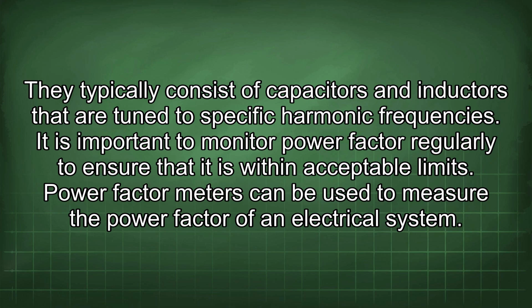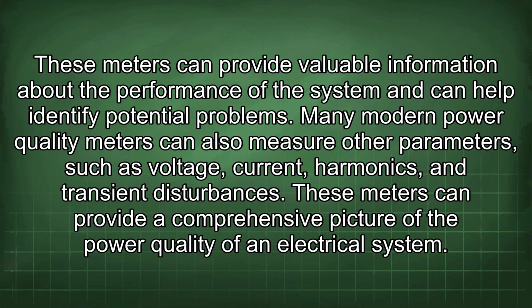It is important to monitor power factor regularly to ensure that it is within acceptable limits. Power factor meters can be used to measure the power factor of an electrical system. These meters can provide valuable information about the performance of the system and can help identify potential problems. Many modern power quality meters can also measure other parameters, such as voltage, current, harmonics, and transient disturbances. These meters can provide a comprehensive picture of the power quality of an electrical system.